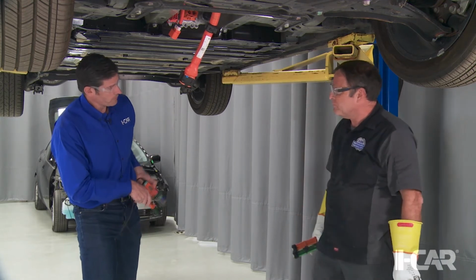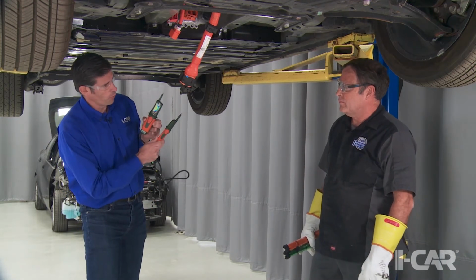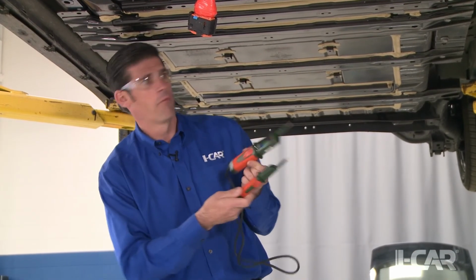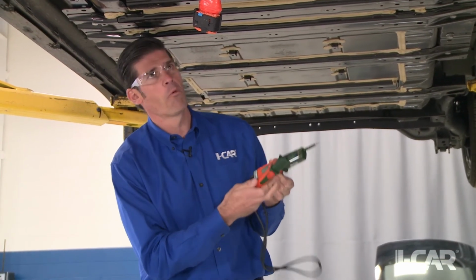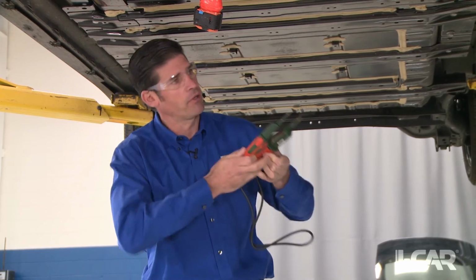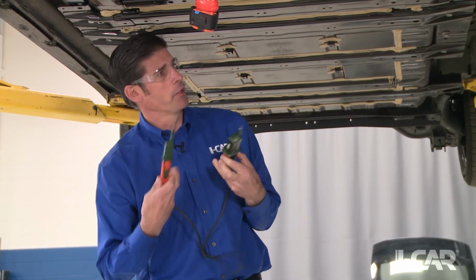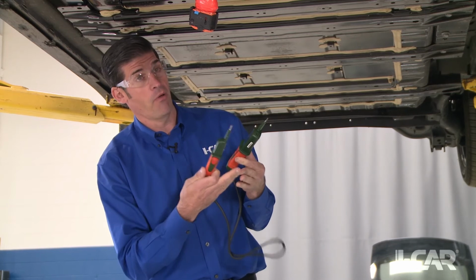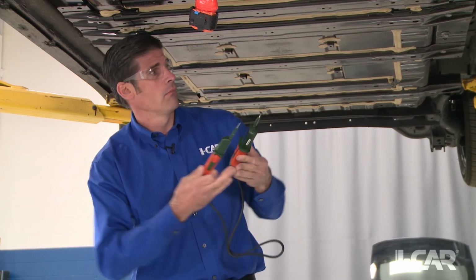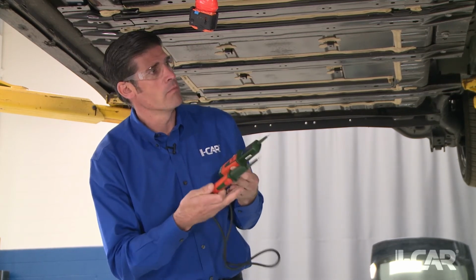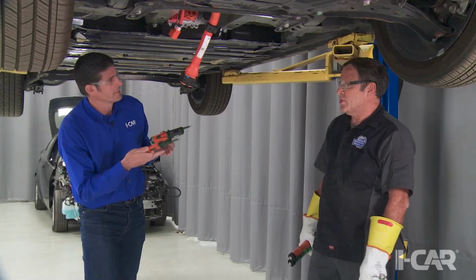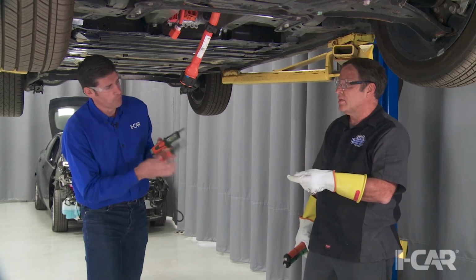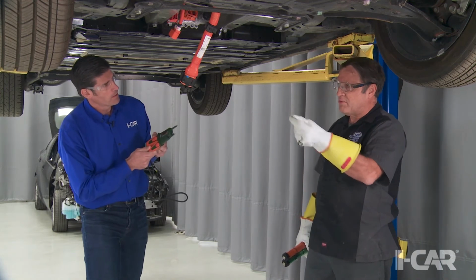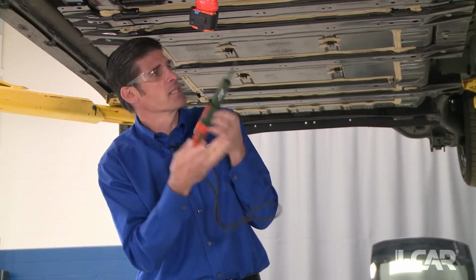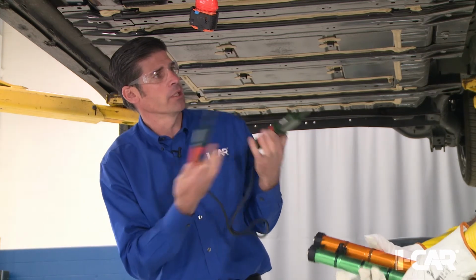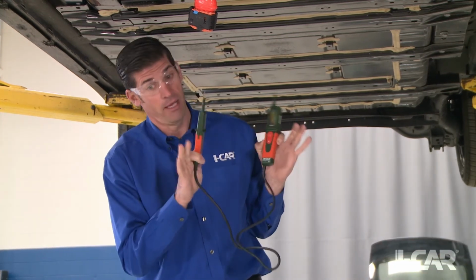Multimeter, 2-pole voltmeter, this shows us 14 volts, not 0.5, 6, 7, 8, whatever. This is not what we're interested in. We want to verify that we're in a low voltage area, below 60 volts minimum. We're not looking for accuracy, but generally within a volt or two, we want to see it show 0, of course, not 400. If it shows 400, we have a problem.